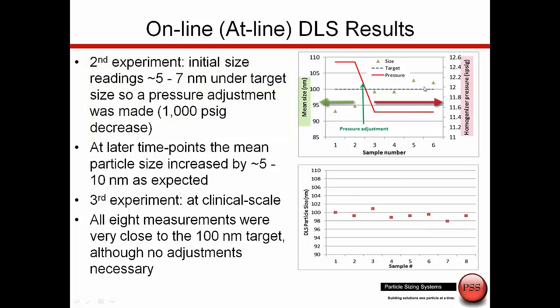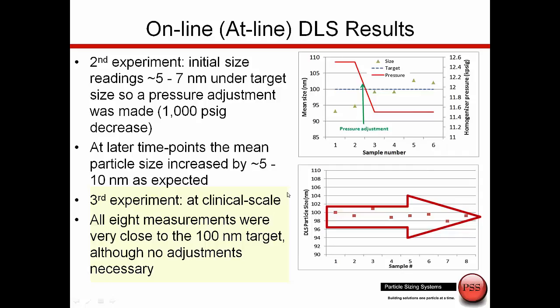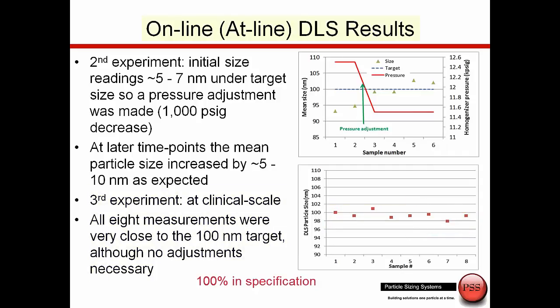Once the relationship between homogenizer pressure and particle size was understood, we could start using the instrument for process control. Here we see particle size on the left and homogenizer pressure on the right. At the beginning, the particle size was at 93 nanometers — a bit smaller than the desired 100 nanometers. By reducing the homogenizer pressure, we could get the particles right up into the desired size range, and then control particle size very tightly over the entire batch. These are very high value batches, and using online size measurement ensures 100% of the batch is within control — something you really can't do by taking samples to a lab.